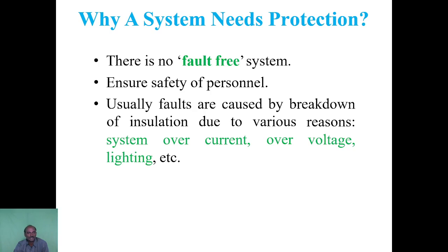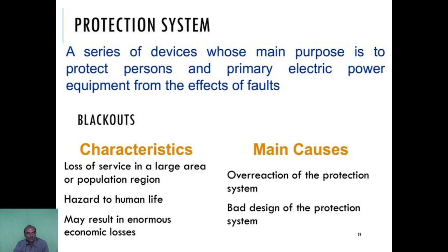We need the power system components. Protection system. It is a series of devices whose main purpose is to protect persons as well as the primary electric power equipments from the effects of faults. So various characteristics and the main causes. Loss of service in a large area of population region. Hazard to human life. It may result in enormous economic losses. The main causes are overreaction of the protection system, the bad design of the protection system.